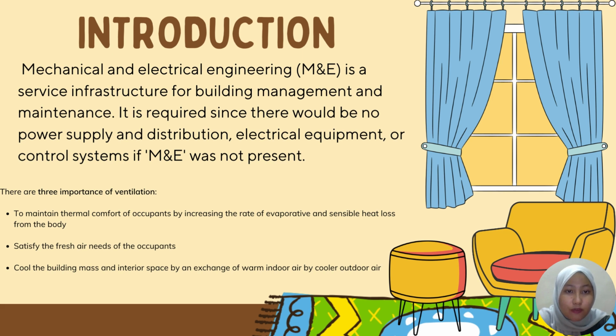There are three importance of ventilation. First, to maintain thermal comfort of occupants by increasing the rate of evaporative and sensible heat loss from the body, like control of indoor air temperature and control of humidity. Second, satisfy the fresh air needs of the occupants, like to maintain air purity and improve human comfort condition. And the last one is to cool the building mass and interior space by an exchange of warm indoor air by cooler outdoor air, when appropriate, and prevention of heat concentration from machinery, lighting, and people.